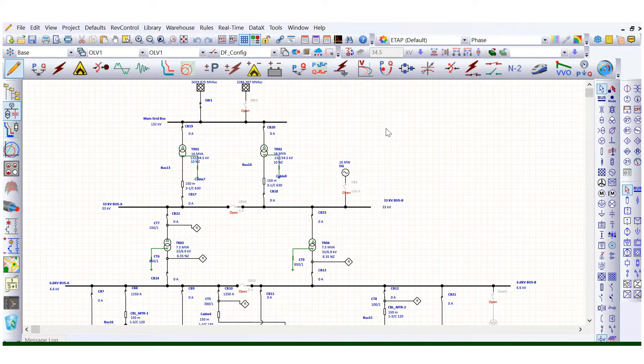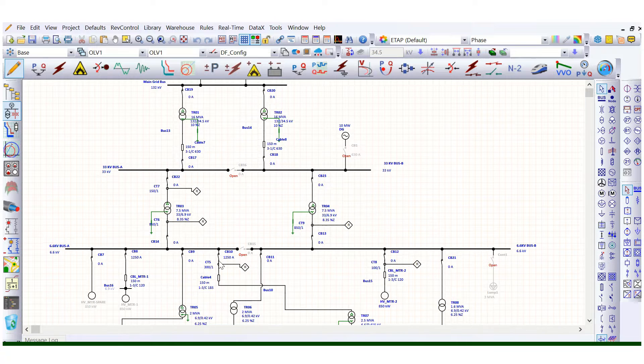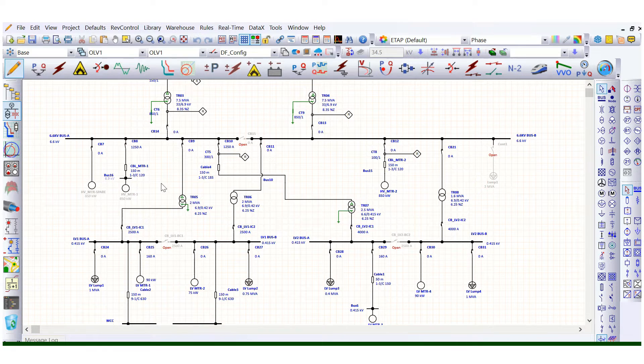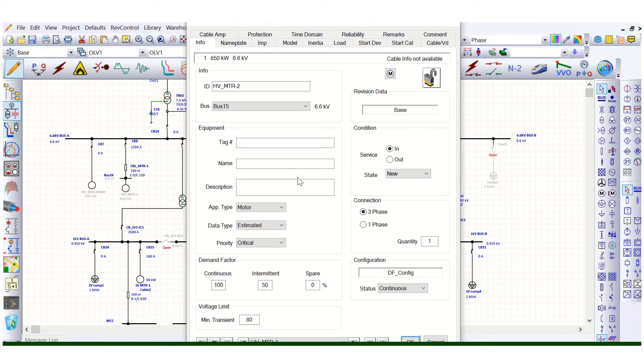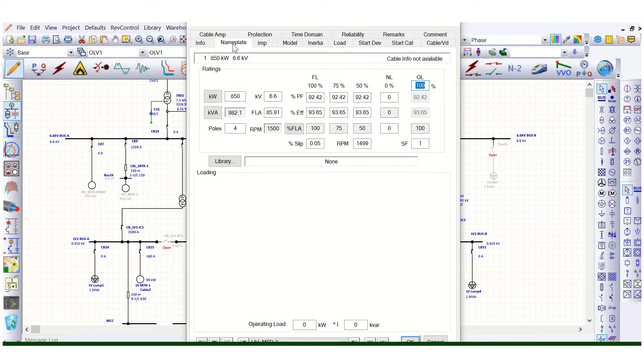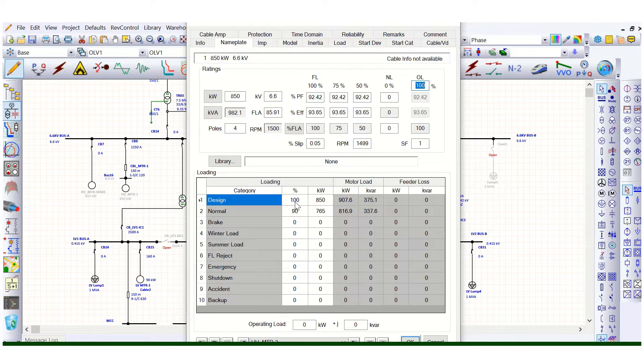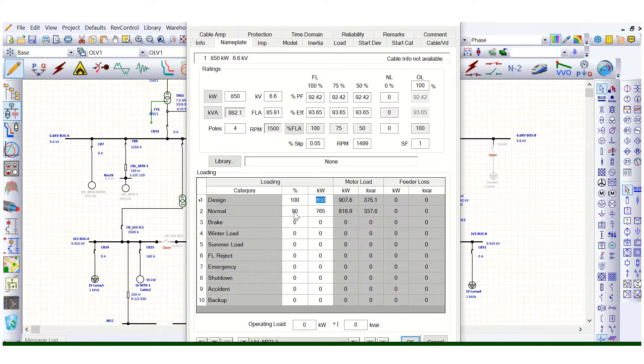In this video we will see how to apply the load diversity factor and also the connected loads. As per the load list, if we assign these loads, let's say this is an 850 kilowatt motor nameplate rating, so this is 100 percent load and 850 kilowatt is the connected load. But if we see what is the absorbed load, the actual absorbed load, that may be 90 percent, 60 percent, 80 percent, or 85 percent.